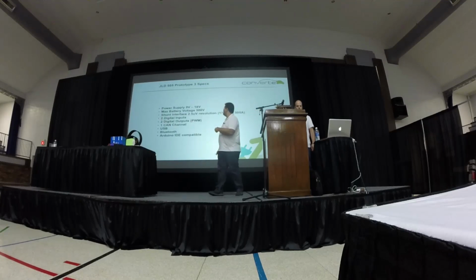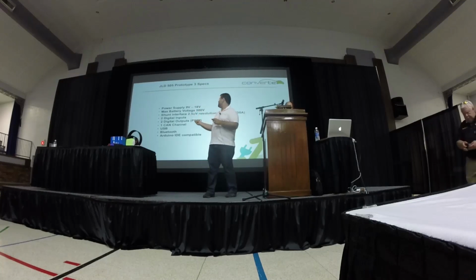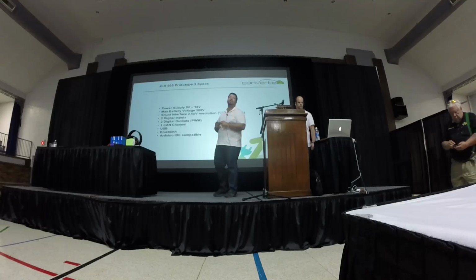What shunt millivolts did you select for? Most Japanese or Chinese ones use 75, the Americans too. You can use any shunt up to 3 volts at voltage on the shunt. How much is it? Depends on your shunt. If you have a 10,000 amp, 75 millivolt shunt, your only limitation is the resolution. This is a fixed value, 2.5 microvolts is fixed. Depending on your shunt, you will have the actual resolution in amps.